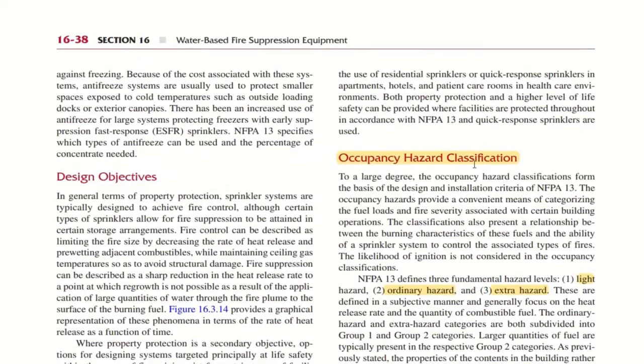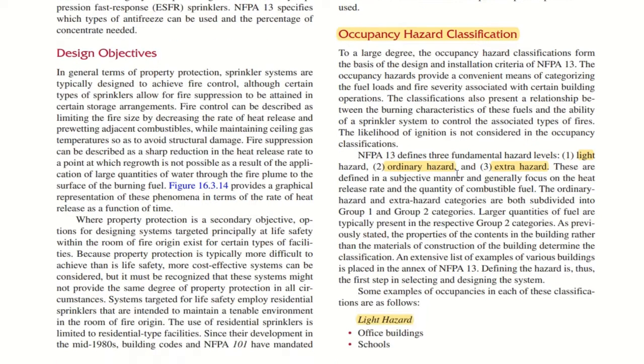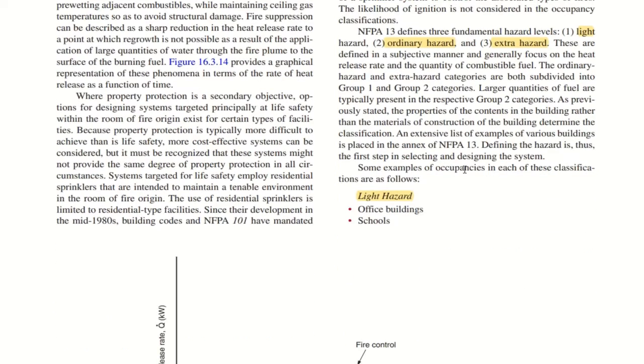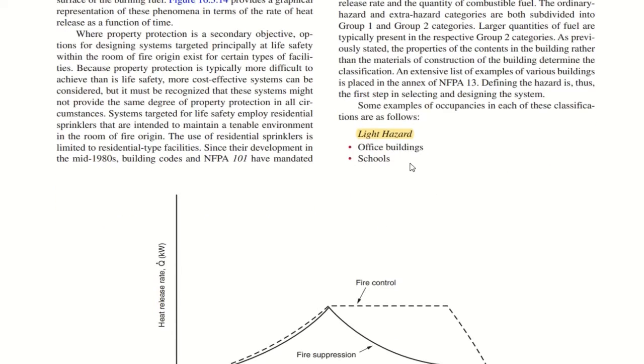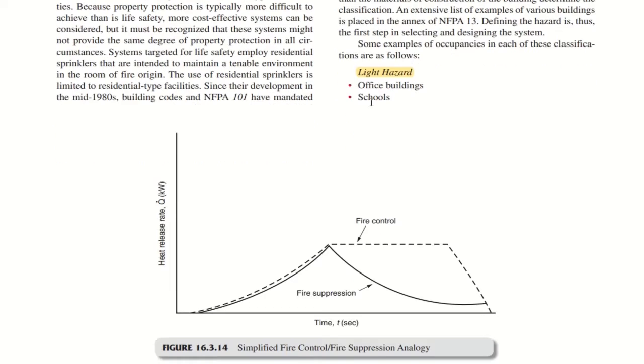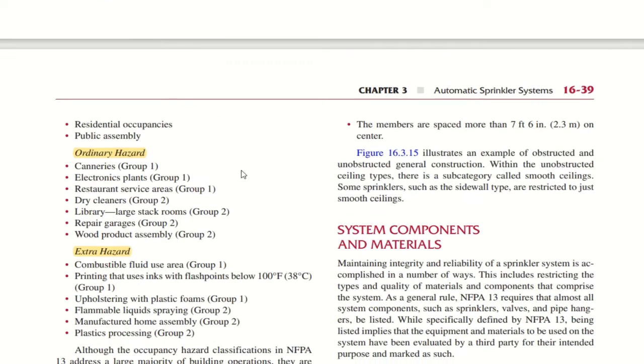Design objectives: they have shown occupancy hazard classification. This is also covered in my NFPA 13 video series. Basically NFPA 13 defines 3 fundamental hazard levels: light hazard, ordinary hazard, and extra hazard. Ordinary hazard is also divided into ordinary hazard group 1 and group 2, and extra hazard into group 1 and group 2. Some of the examples which are already available in NFPA 13 are shown here too. Like light hazard: office buildings and schools come under light hazard. Residential occupancies, public assembly.